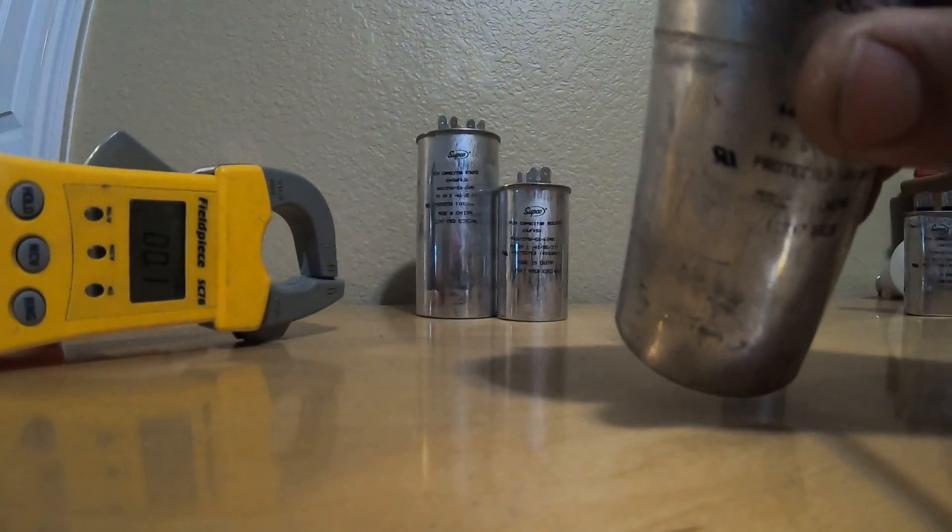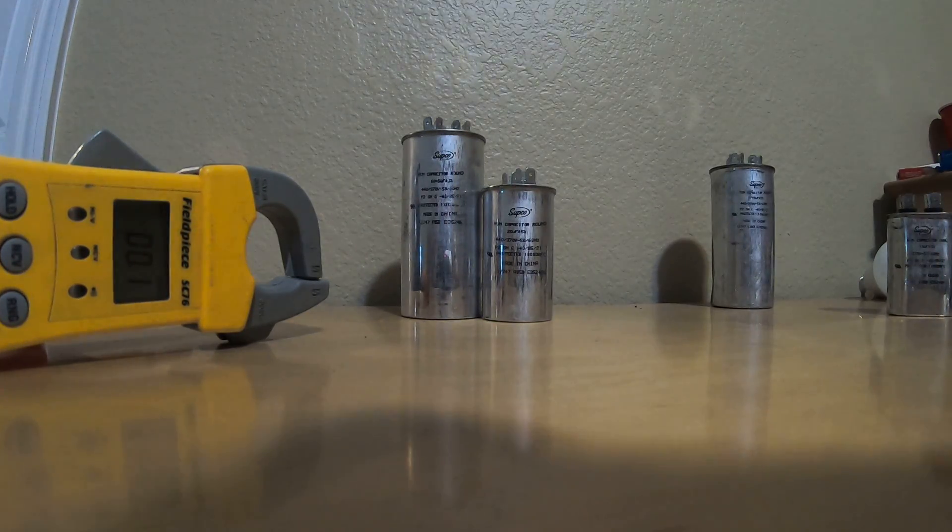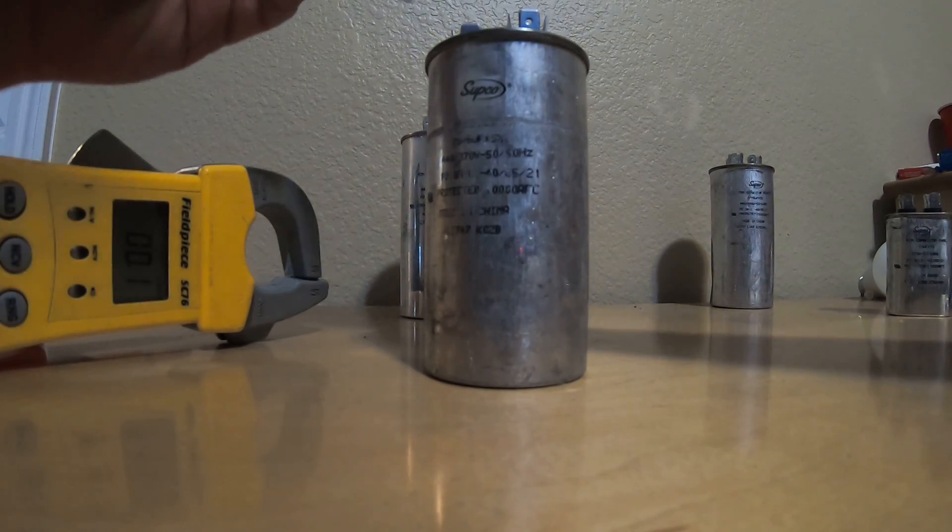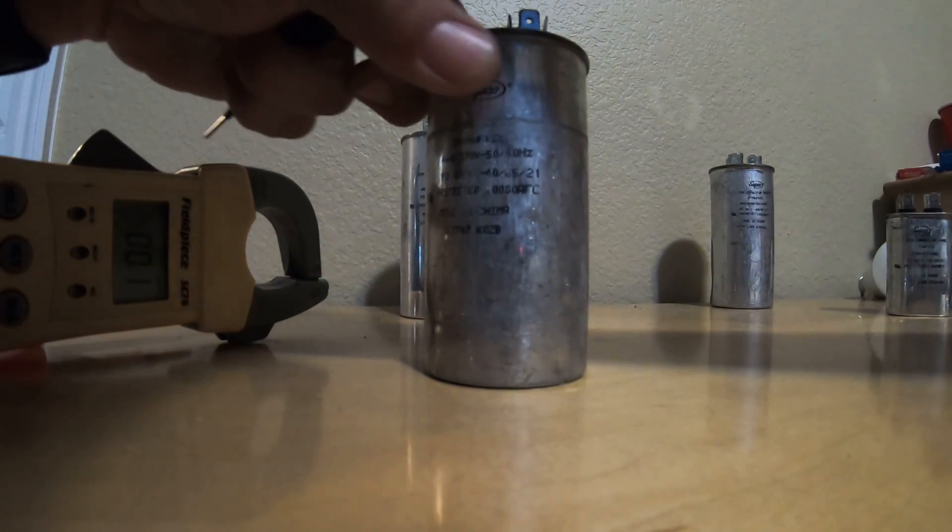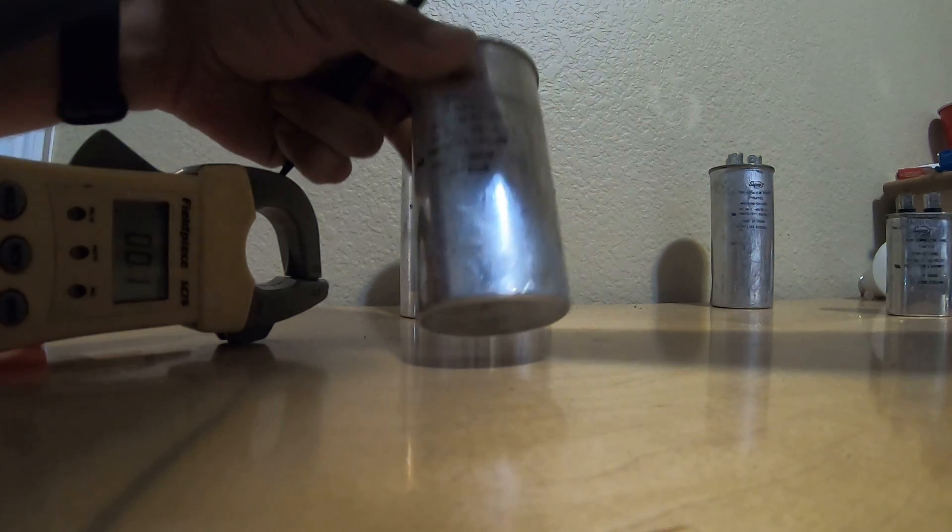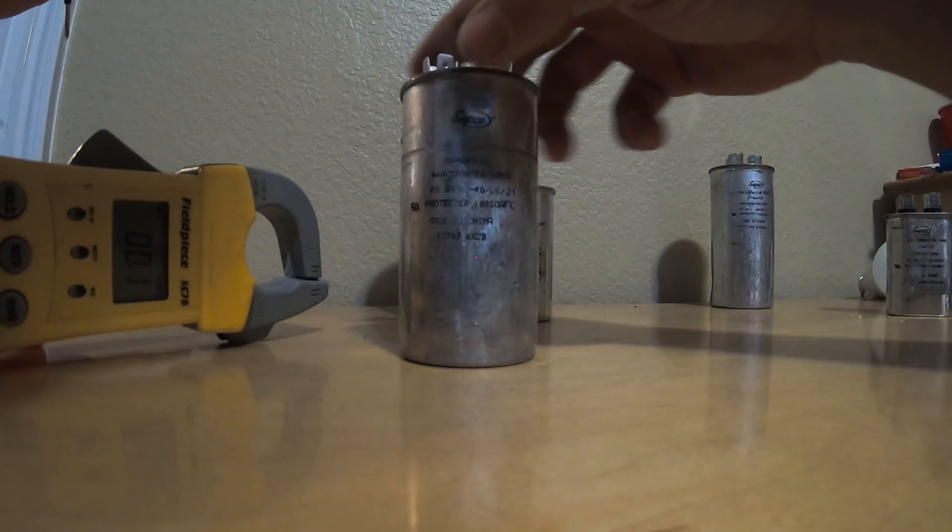I would never try to take that and say, well I've got a condenser fan motor that needs a 5 microfarad capacitor and put that 10 on there that's now reading a 6. I've seen guys do that and it does not work.